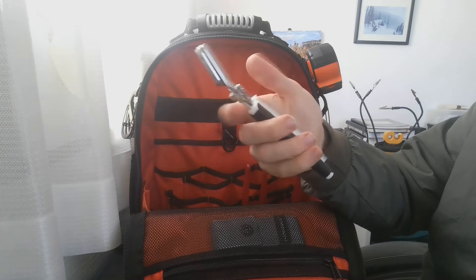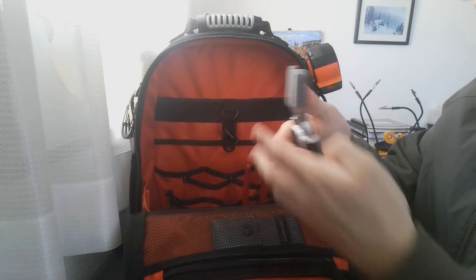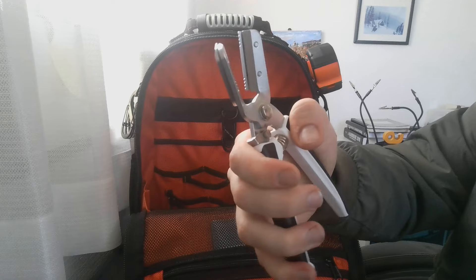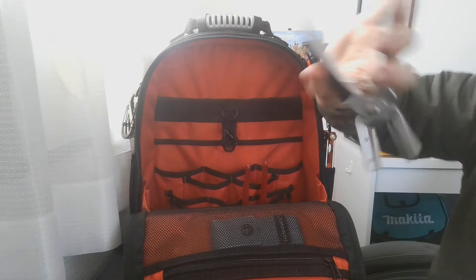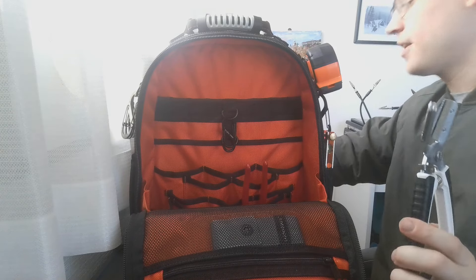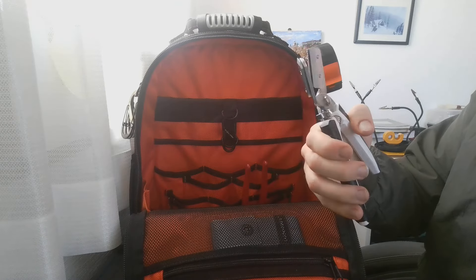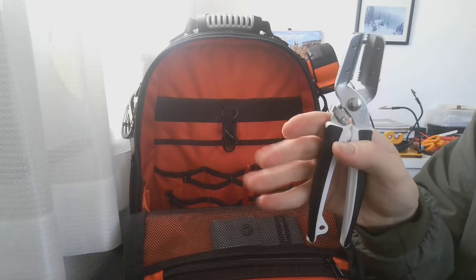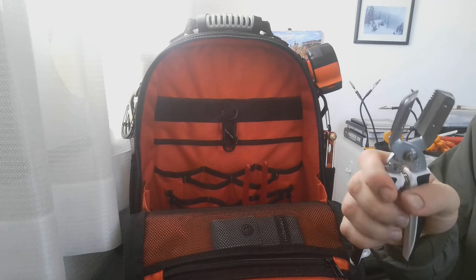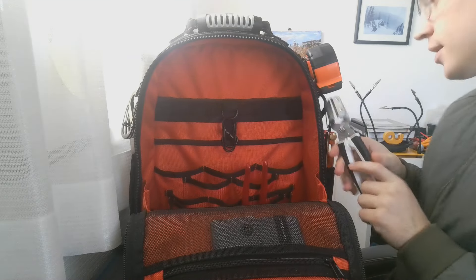And then I have these beauties — the Tajima DKMC40. These are for stripping large cable. You grip on and move it around. It's a bit harder than using a tool that freely spins, but this works like a charm — you can cut through things so easily and just have to spin it a little bit and then pull the Romex sheath off. The only challenge is if you get your grip length wrong you can cut through the insulation on the wires themselves or nick the copper. But that just takes some skill and I'll get it down. I really like these because they actually work.